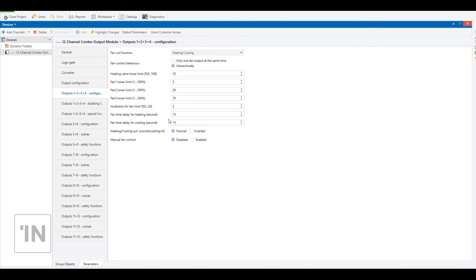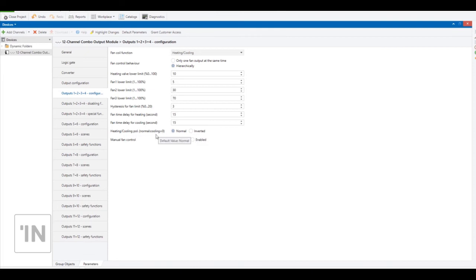You can arrange that delay time. Heating/cooling polarization: it works with zero normally for cooling, and you can invert that value — make it one for cooling. For manual fan control, when you send the value two for example, it opens fan level two directly. When you disable manual fan control, fan levels open depending on your set point temperature.